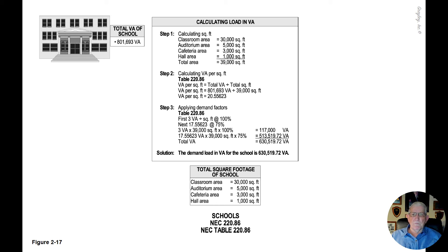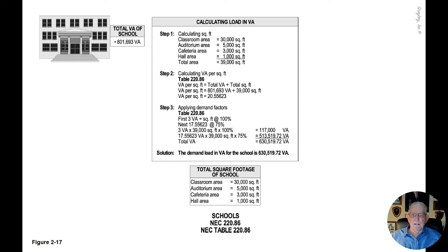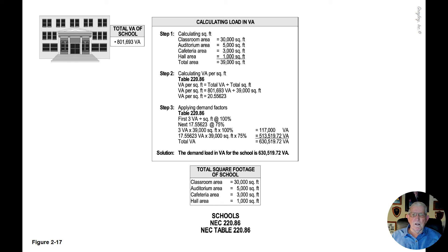Step two, we're calculating the VA per square foot per table 220.86. So the VA per square foot is equal to the total VA divided by the square foot area.